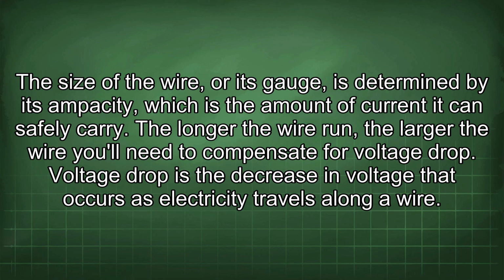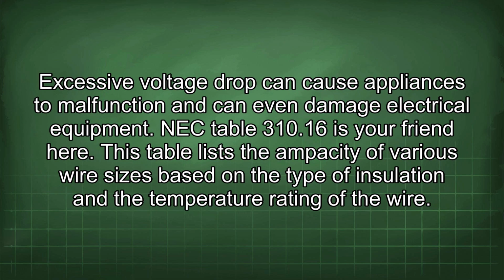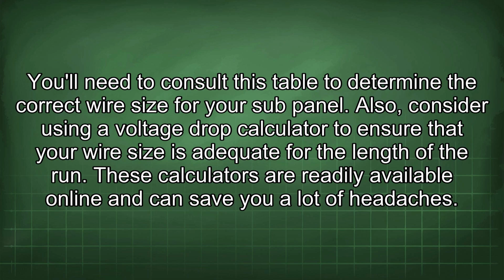Voltage drop is the decrease in voltage that occurs as electricity travels along a wire. Excessive voltage drop can cause appliances to malfunction and can even damage electrical equipment. NEC Table 310.16 is your friend here. This table lists the ampacity of various wire sizes based on the type of insulation and the temperature rating of the wire. You'll need to consult this table to determine the correct wire size for your sub-panel. Also, consider using a voltage drop calculator to ensure that your wire size is adequate for the length of the run. These calculators are readily available online and can save you a lot of headaches.